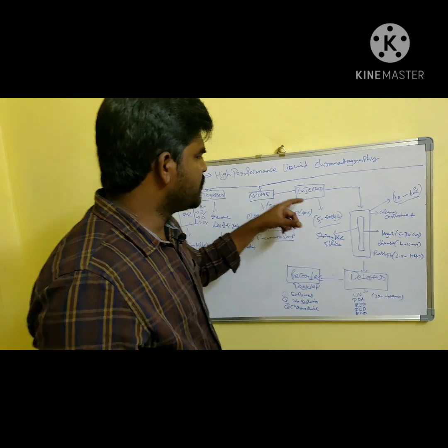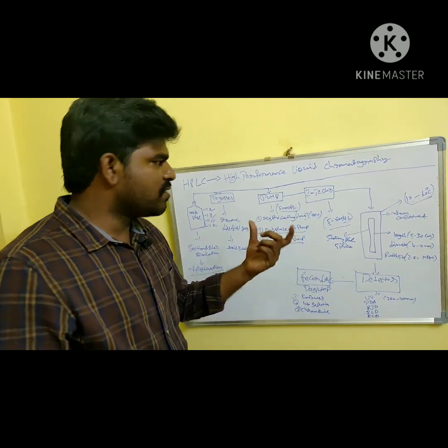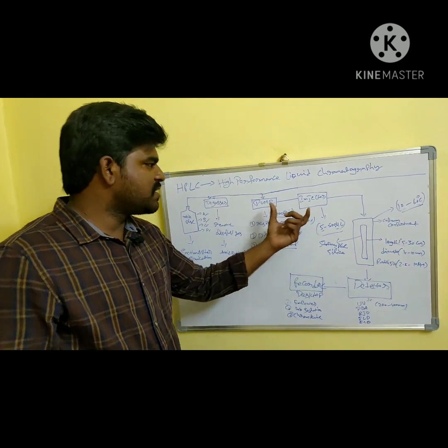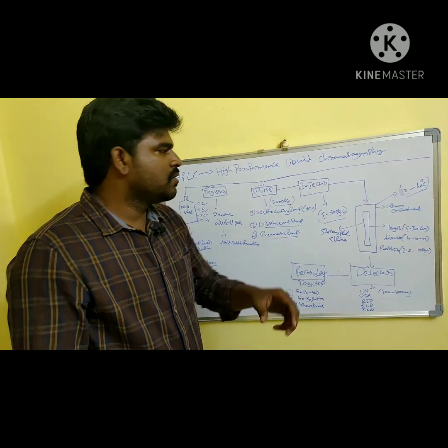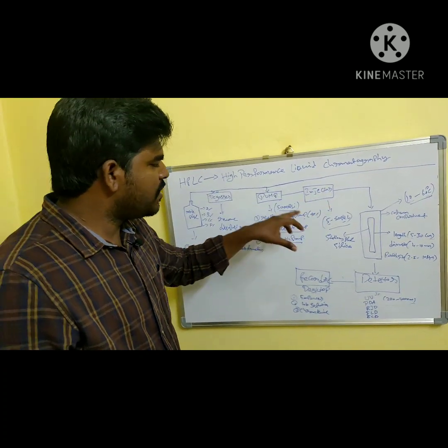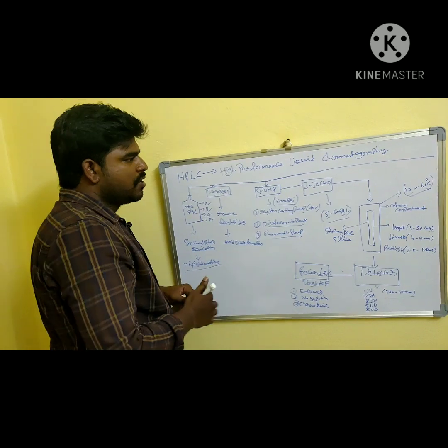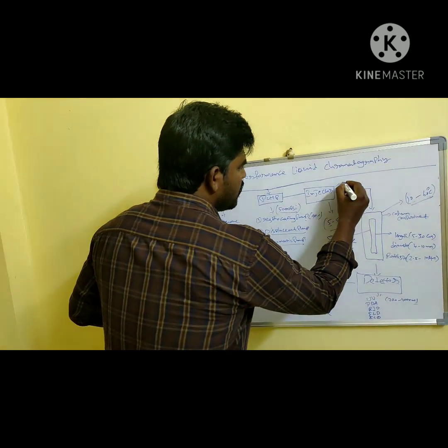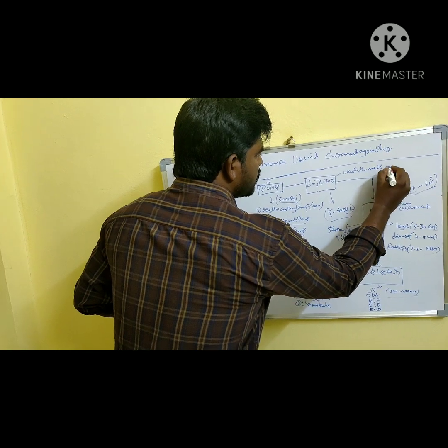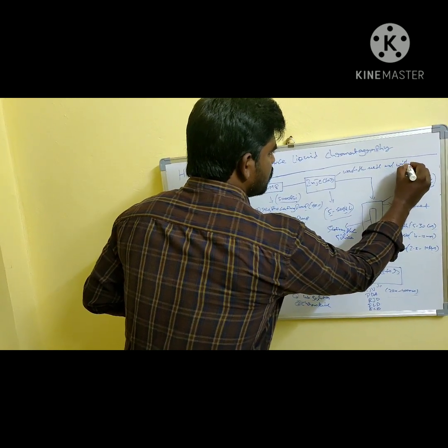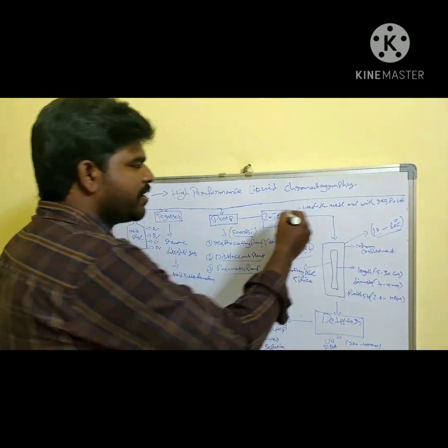And when coming to the injector, whenever you are injecting high concentration samples, it may lead to product carryover to another product. To avoid that, we need to take the needle wash. We need to wash the needle with the respective solvent to avoid carryovers.